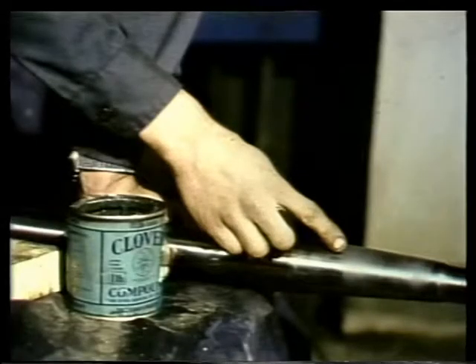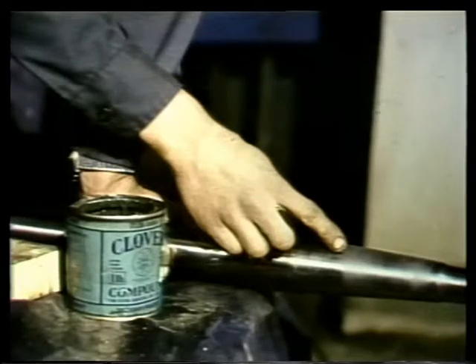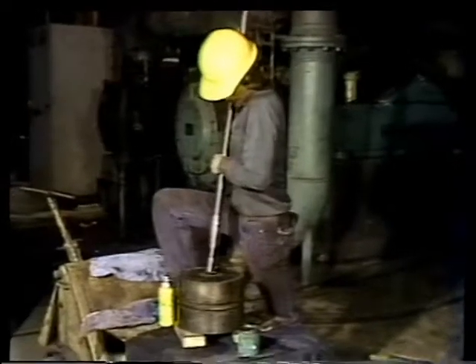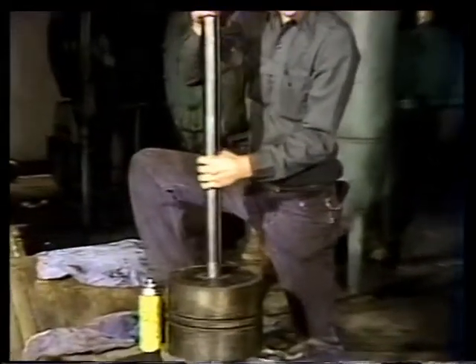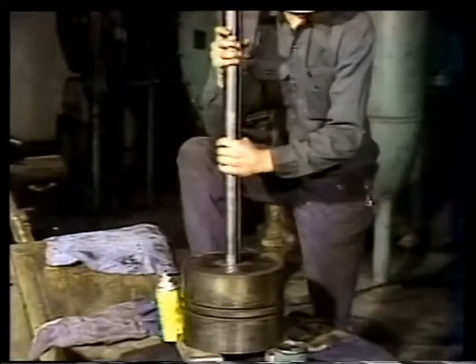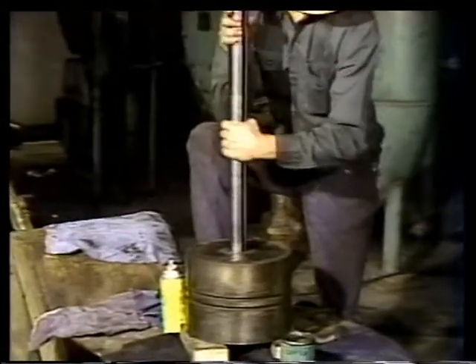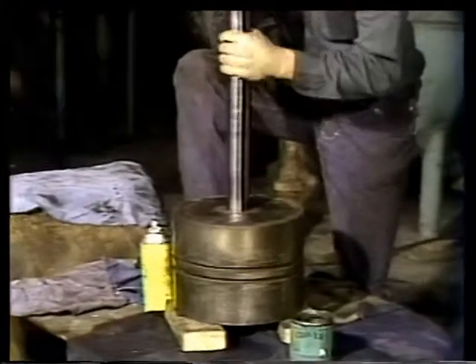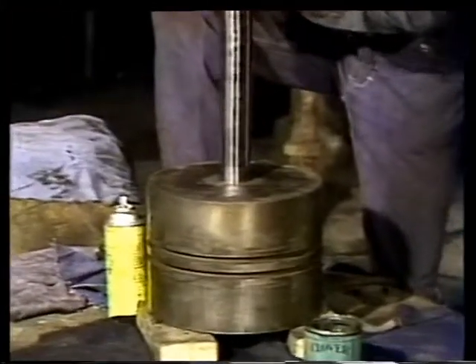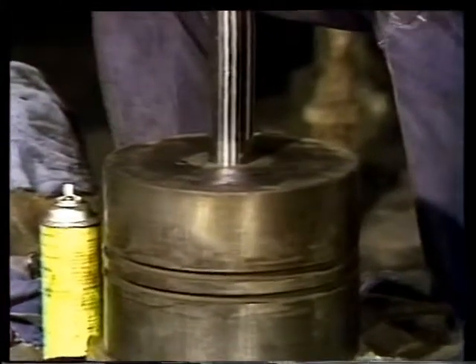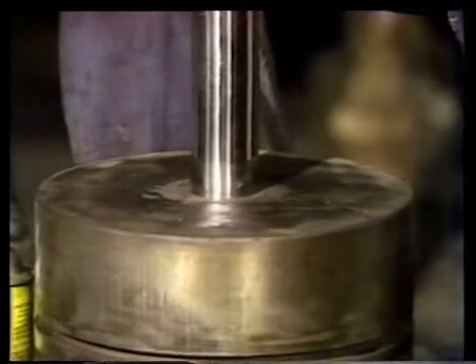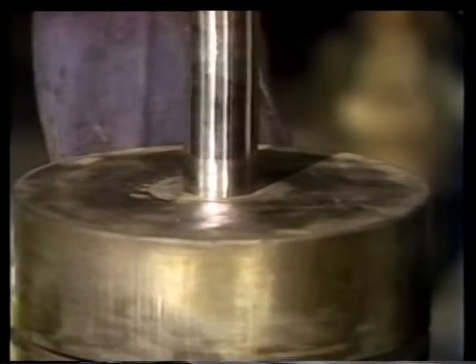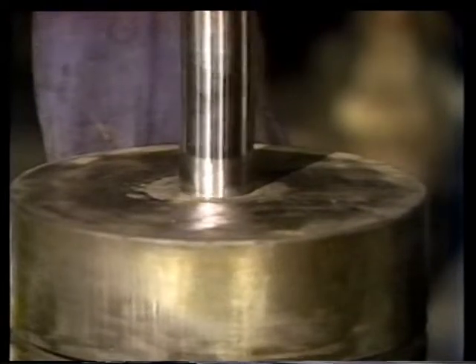To begin the grinding in process, put a few dabs of a coarse lapping compound on the piston rod. Then insert the piston rod into the piston and begin to rotate the rod back and forth. When the back and forth motion between the piston and piston rod becomes easier and smoother, that's an indication that the lapping compound has worn down and needs replacing.